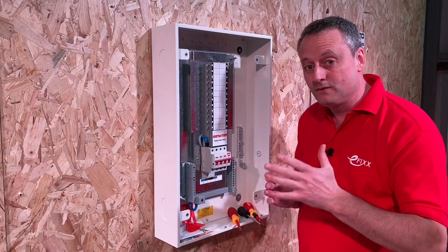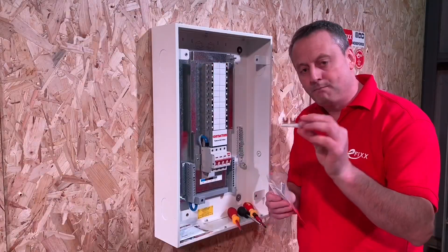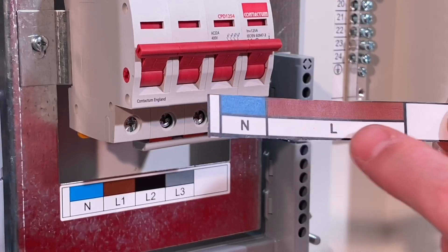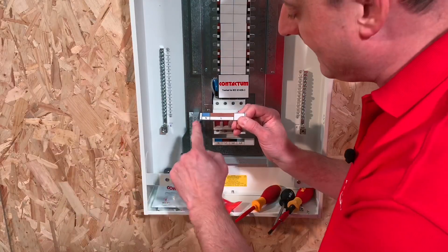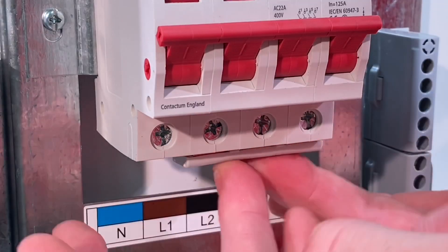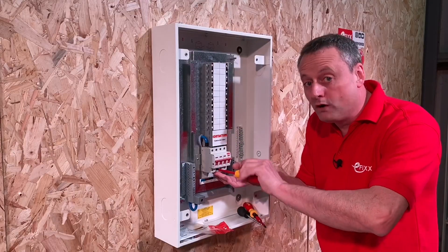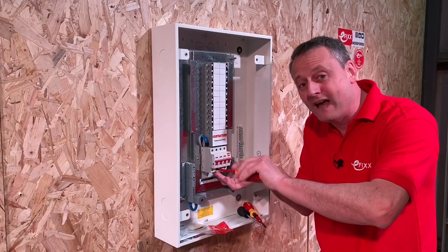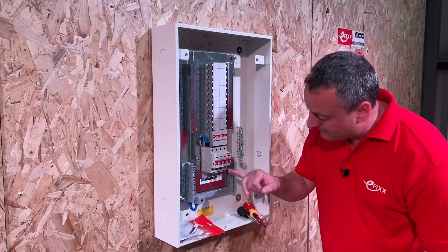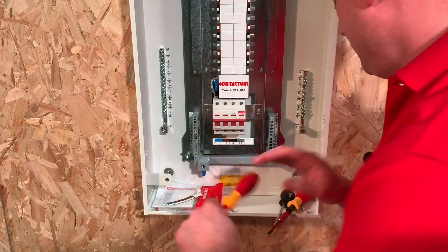This is currently a three-phase distribution board. I've got a conversion kit in this packet — it's simply a bar to strap across the three line conductors, plus a replacement sticker for the consumer unit showing all conductors in the same color, meaning one line and one neutral. You put the bar in the right place strapped across the line. Your incoming cables — one line and one neutral — come into the bottom here, and it wouldn't matter which of the three holes you use for the line. The neutral follows through to the neutral bars.